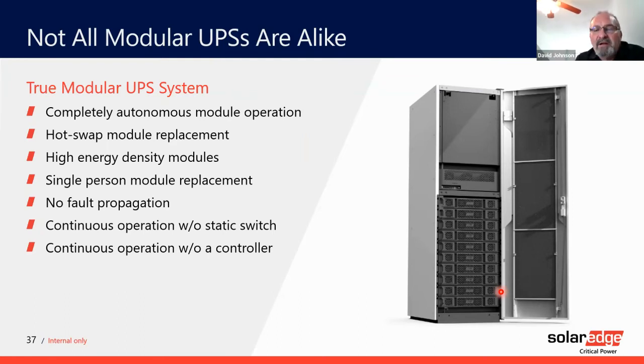High energy density modules—I mentioned 44 pounds. We offer several different versions depending on whether it's 120, 208, or 480. Single person module replacement based on the weight, no fault propagation. If a unit fails, it's not going to cause all the others to fail—it will take itself offline, and as long as you have redundancy, a minimum of N+1, the system continues to function. We can have the static switch fail within the system, and it still functions without the static switch. At some point you'll have to replace that, but it won't take the system down.